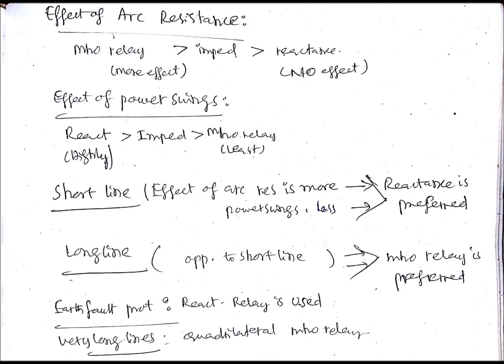The effect of power swings is completely opposite to that of the effect of arc resistance. So the reactance relay is most affected by power swings, while the mho relay is least affected by power swings.